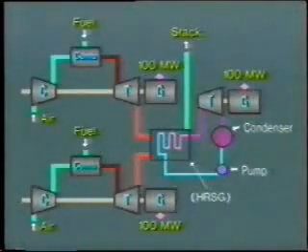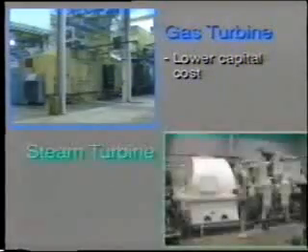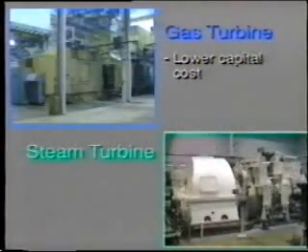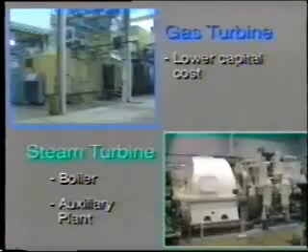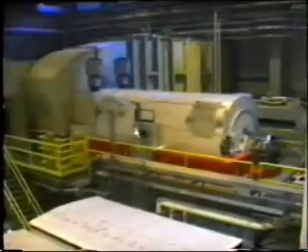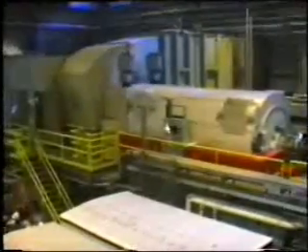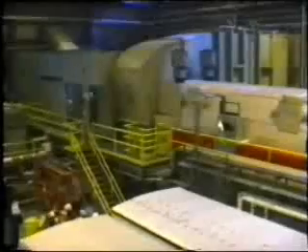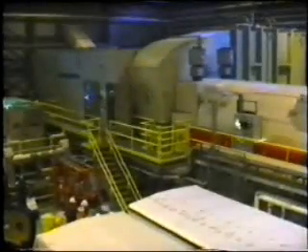The combined cycle also offers an economic gain. The capital cost of installing a gas turbine generator is much less than the equivalent steam turbine installation with its associated boiler and auxiliary plant. Yet another advantage is that the gas turbine can be installed and be available for operation in far less time than the conventional steam plant. So you can see many reasons why power companies are currently installing gas turbines and combined cycles.